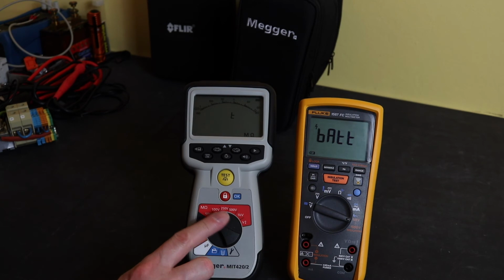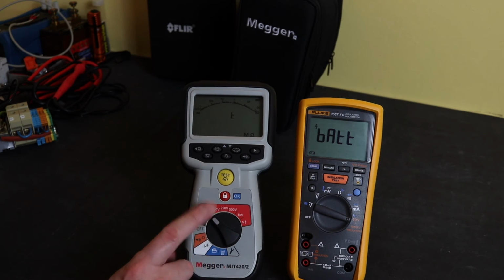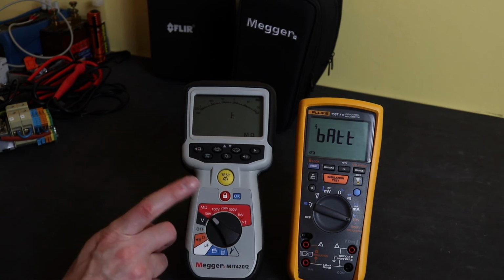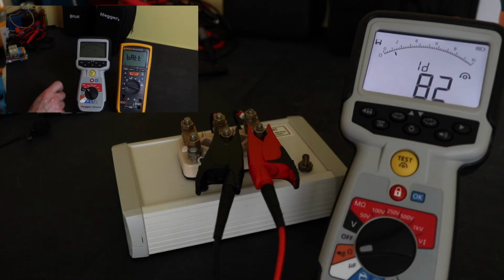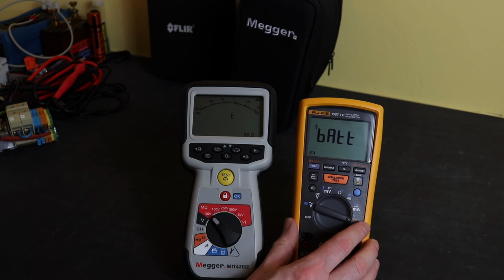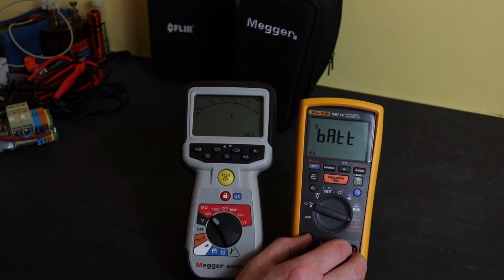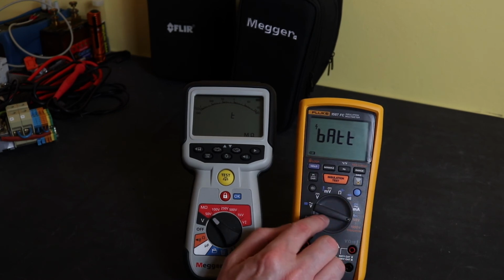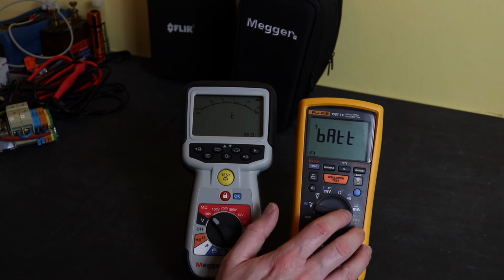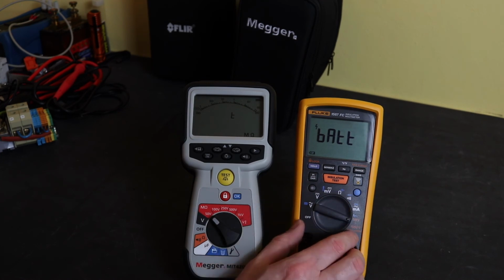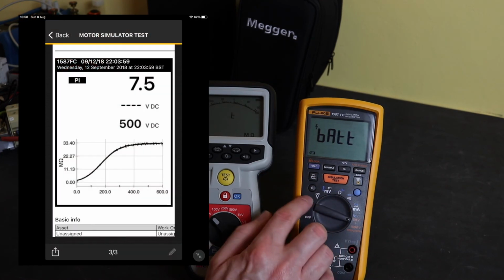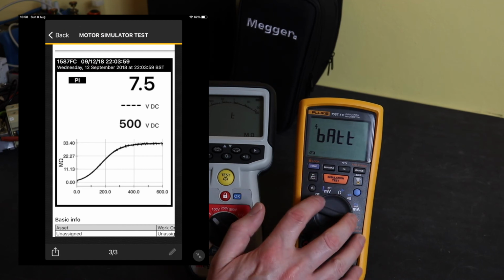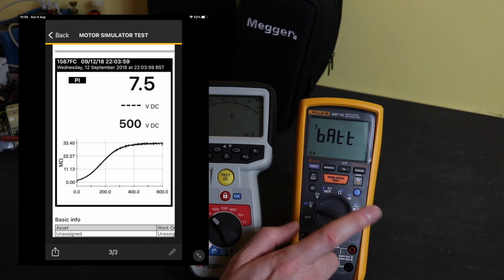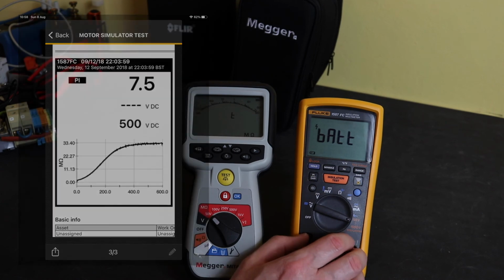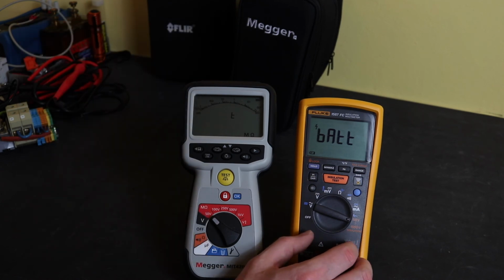The Megger has built-in memory. To save a reading, you just hit the save button and it saves it to the next allotted data number. The 1587 doesn't have any built-in memory, but it does have Bluetooth connection to an iPad, and you can record readings, you can record the PI and the DAR curve, you can voltage log, you can current log, and you can save all those readings and you can put them into a report.